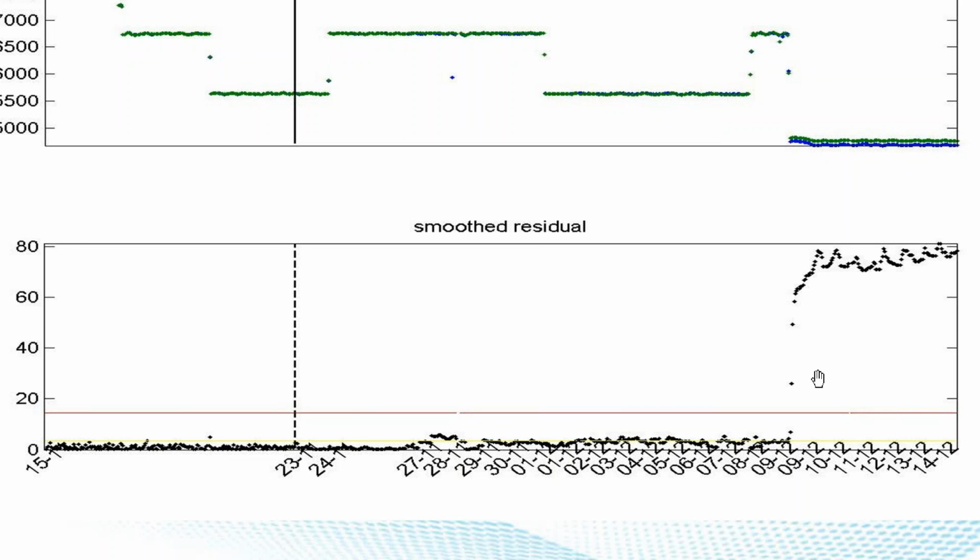So what we provide is this early alert about escalating defects. Since they gave us only 1 month, we only made this identification 2 weeks before the leakage started. On average, our rate in detecting a leak before it starts is 42 days. So it's a month and a half. And of course, the leakage is right here. So training stage, testing stage, and 2 thresholds, the sensitivity of which we determine together with the client.